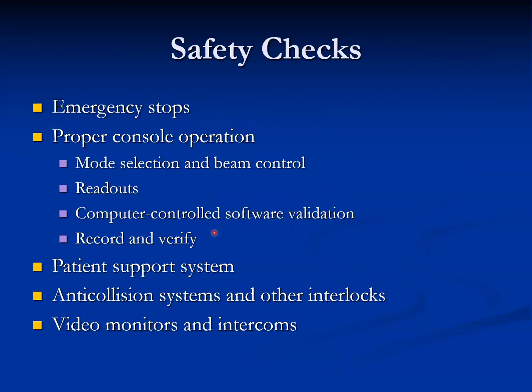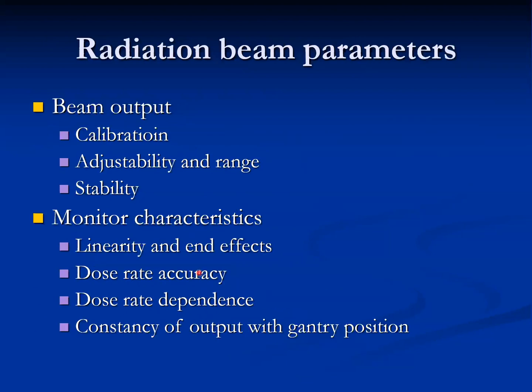Safety checks include emergency stop, proper console operation, mode selection, beam control, readout, computer control software validation, record and verify system, patient support system, anti-collision system, and other interlocks. Video monitors and intercoms should also be available.